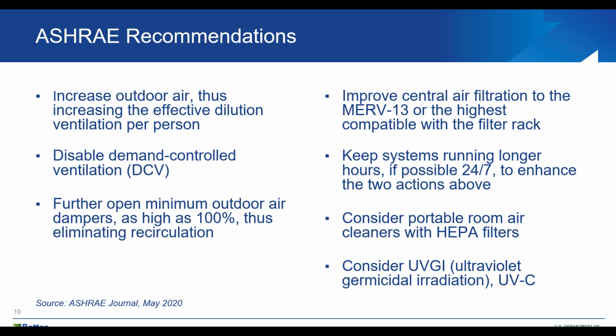ASHRAE has several recommendations of how to operate the building. Again, this is more about how we react to what ASHRAE recommends. A lot of what you see on the left side has to do with outside air, increasing ventilation, dilution, demand control ventilation, and what percent outside air. They recommend raising it as high as 100%. And then some of the systems on the right: how do you impact the filtration? Can you raise it as high as MERV 13 or higher? What happens if we want to run the systems longer, or use different flush systems in terms of bringing in more outside air and more air change rates, or adding additional equipment such as portable air cleaners with HEPA filters, or adding a new system to deal with the virus itself, a UVGI or UVC system added to the air handler or in the rooms themselves? So ASHRAE has a lot of recommendations, and how is it impacted under COVID? Next slide, please.